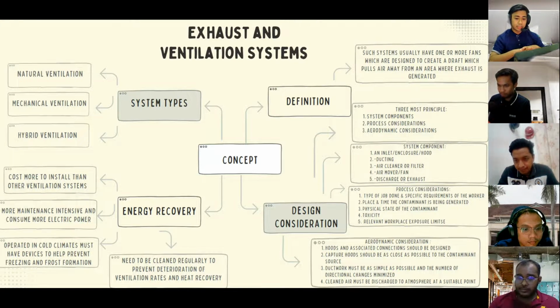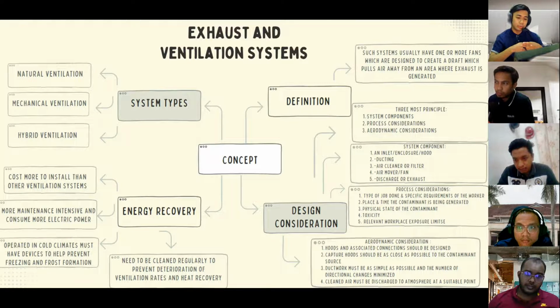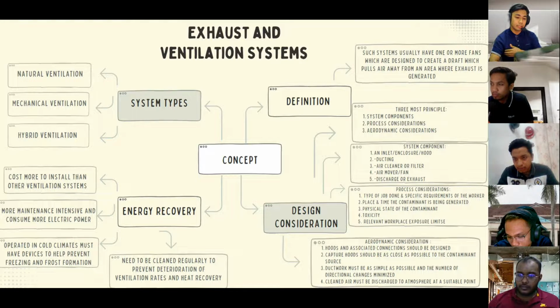The energy recovery ventilation system requires more maintenance than the other ventilation systems. They need to be cleaned regularly to prevent deterioration of ventilation rates and heat recovery, and also to prevent mold and bacteria on the heat exchanger surface. So that's all for me. Thank you.